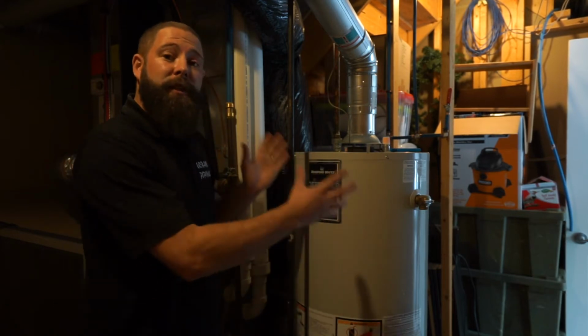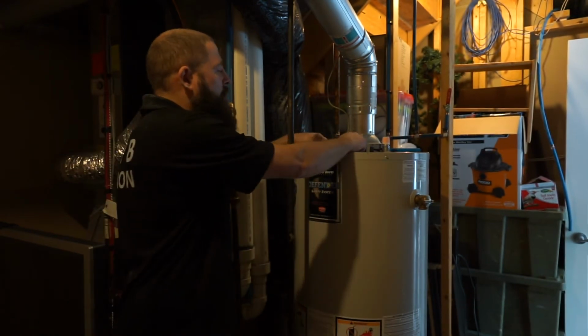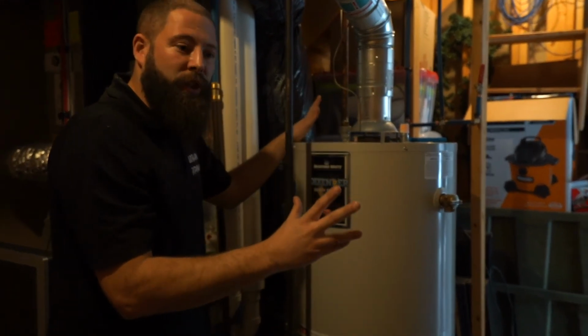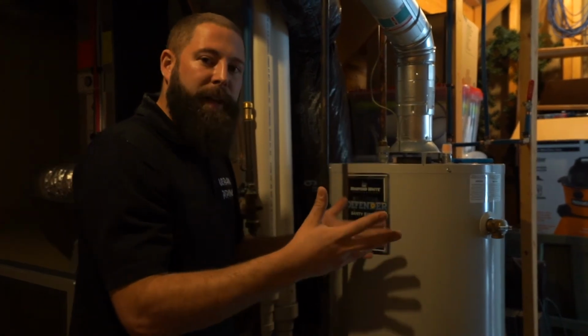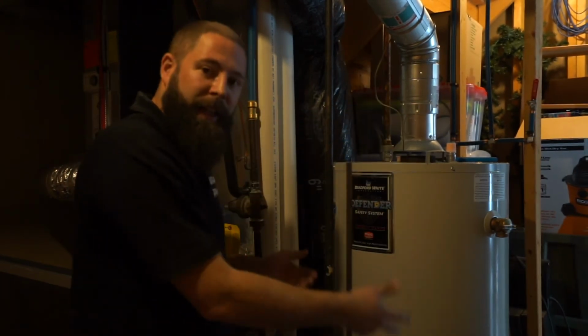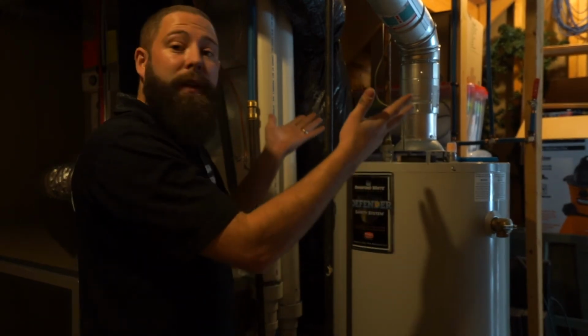And over time, as your tank ages, the constant expansion and contraction of the hot water and cold water in the hot water tank will eventually make a stress crack between the atmospheric vent and the inlet and outlet. Now, this will be a very, very tiny fracture. And when you use your hot water tank, like first thing in the morning, everybody showers, that gap will open up because it's all cold water that's now filled your tank. But that will cause the leaking. But as it heats up over the next hour, the gap will squeeze shut again because you have hot water in there, and then everything will dry up.